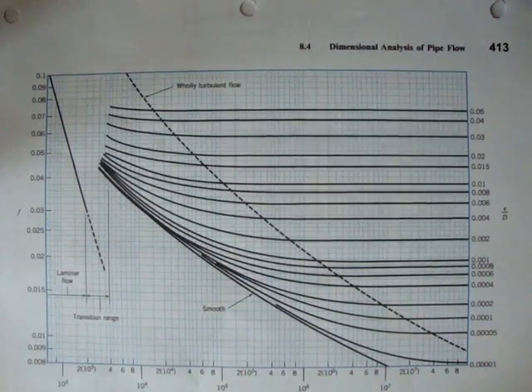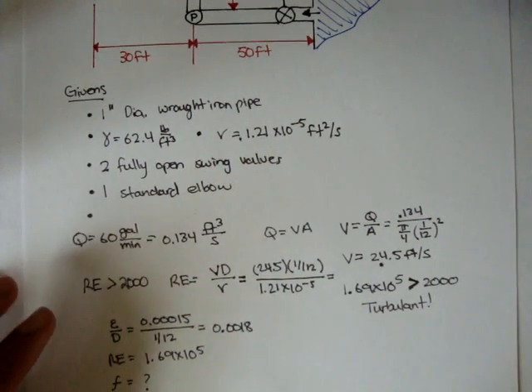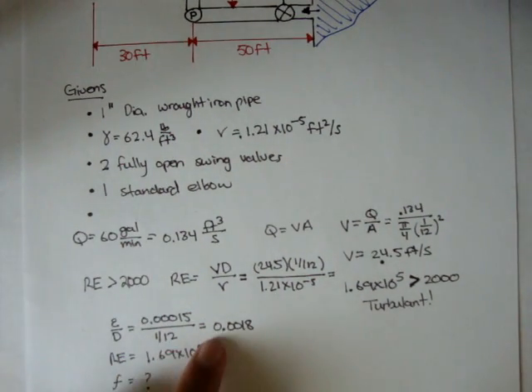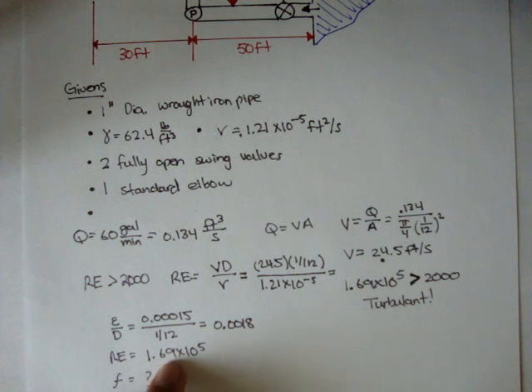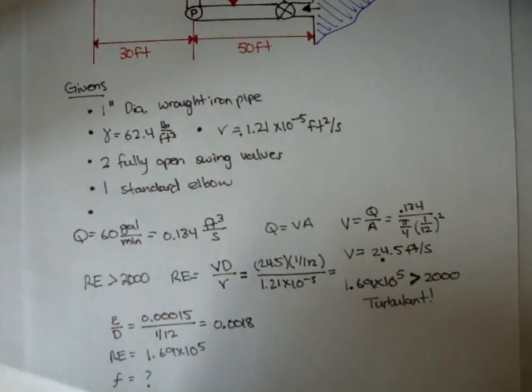Okay, just continuing the example. In the last video we found our relative roughness to be 0.0018, we found our Reynolds number to be 1.69 times 10 to the 5th, and we actually don't know our frictional factor - we'll find that in this video.